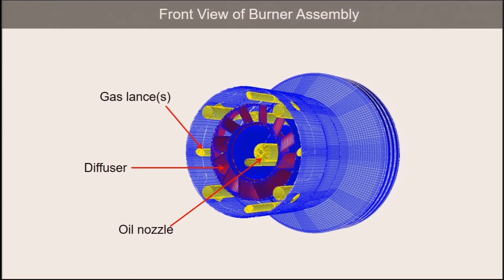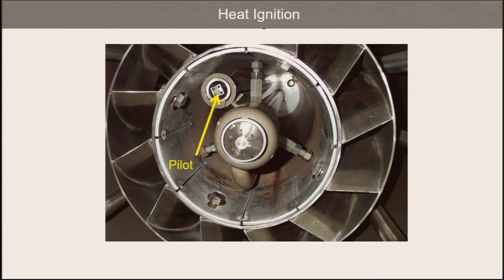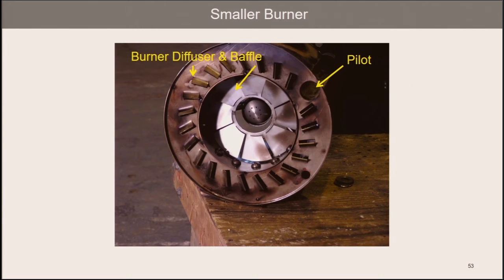We have fuel, air, and turbulence — now we need heat to combust the mix. That comes from the pilot, pictured on the screen, which is lit by an electric spark initially and then stays lit through the main proving sequence, where the flame scanner proves the main flame is stable. Here's another example of a smaller burner that uses both a diffuser and a baffle plate for inducing turbulence for mixing the fuel and air, with the pilot also shown for igniting the mix.